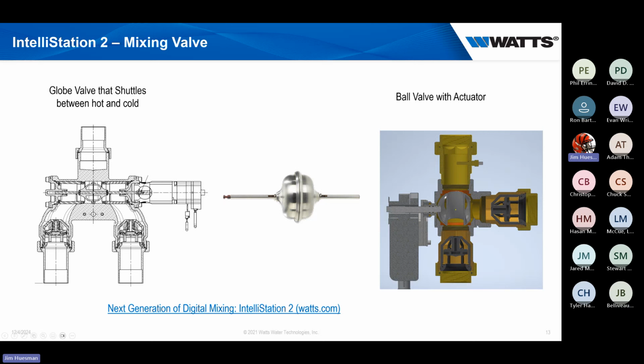So what they've done is ramped this up and added some really decent sized checks that are actually rebuildable. Internally, where we used to have a large ball valve with 3 ports, hot on one side and cold on the other, spinning back and forth, they've redesigned it. Now we're using more of a globe valve shuttle, and this ball inside, all stainless, will actually go back and forth.